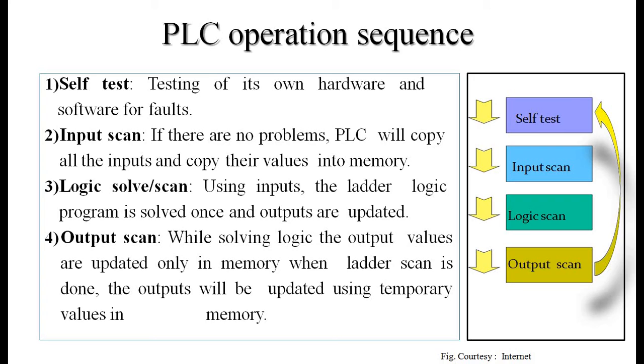Then logic solve or scan takes place. Using the inputs, the ladder logic program is solved once and outputs are updated. According to whatever inputs are updated by the PLC, the program will execute accordingly. While solving the logic, the output values are updated only in memory. When the ladder scan is done, the outputs will be updated using temporary values in memory.